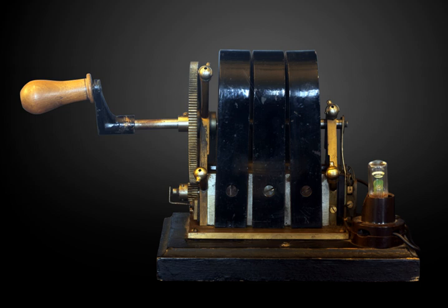The development of modern rare-earth magnets makes the simple magneto-alternator a more practical proposition as a power generator, as these permit a greatly increased field strength. As the magnets are compact and of light weight, they generally form the rotor, so the output windings can be placed on the stator, avoiding the need for brush gear.